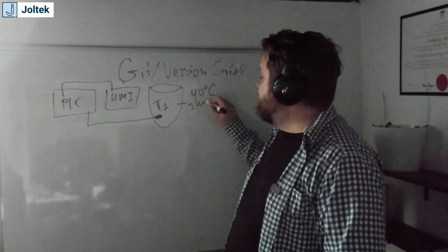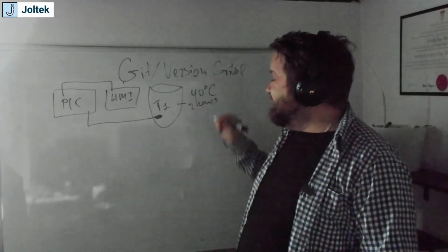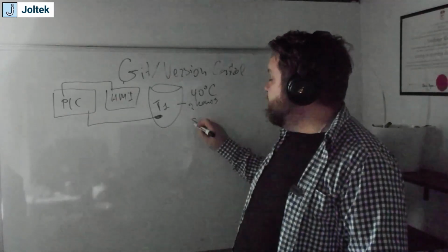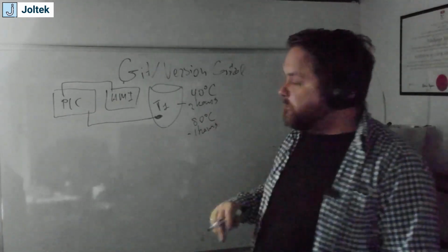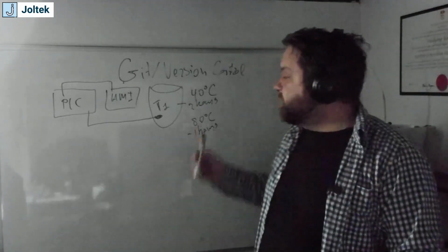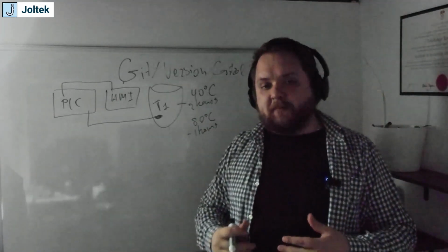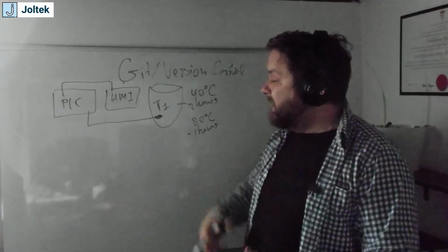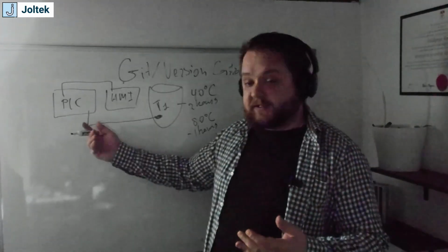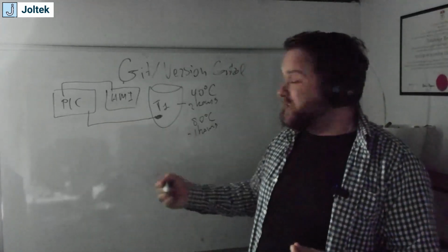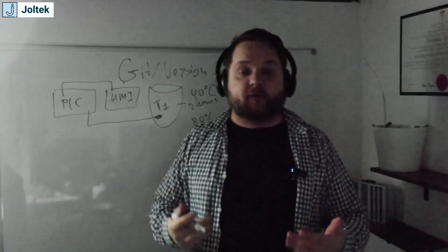So 2 hours, it's nearly room temperature, slightly above that. And then for a different batch, it needs to be set to 80 degrees Celsius, and it needs to be for 1 hour. So the problem here is that these variables or these registers are not necessarily part of what's called the PLC program, right? So the programmer has created a routine and a set of logic files that will be put on the PLC with the intent that the registers can be set to whatever they need to be set via the HMI by the operator for that specific batch.